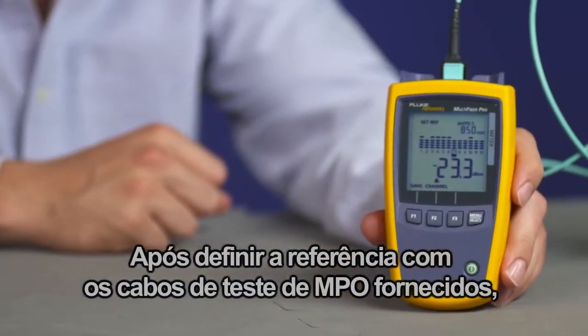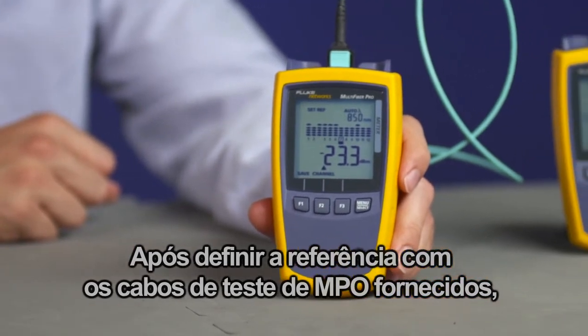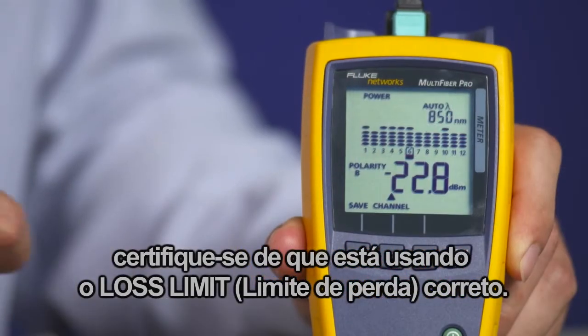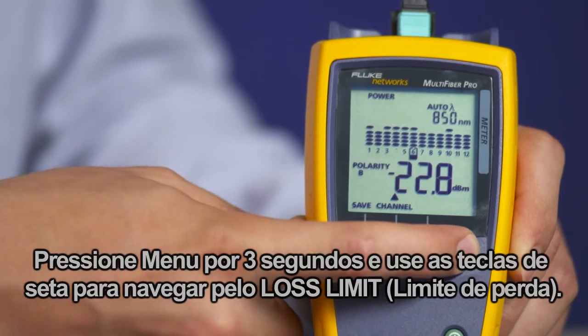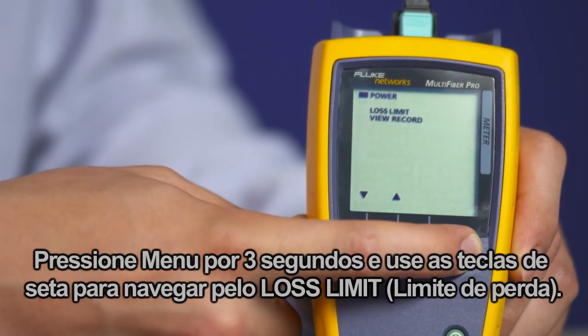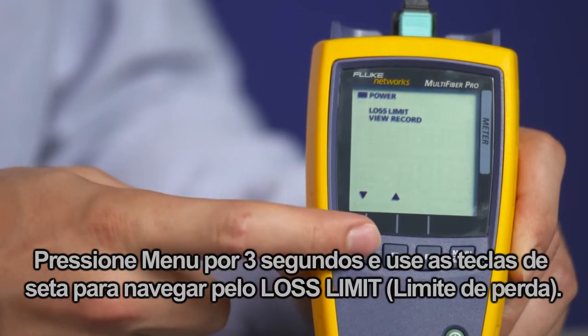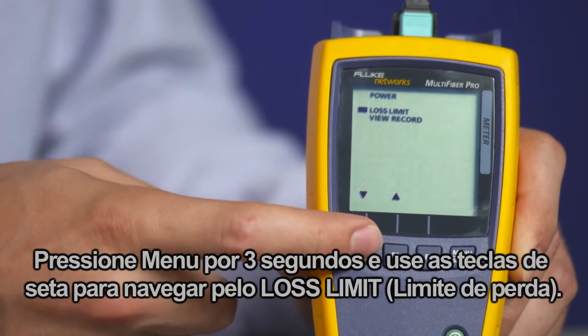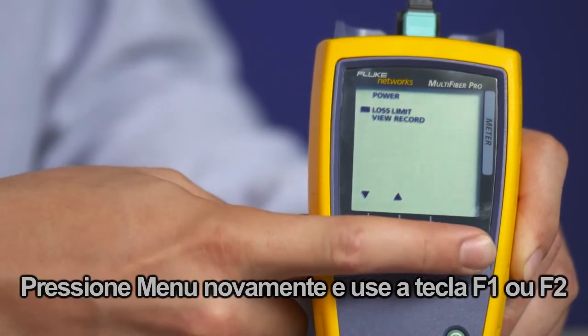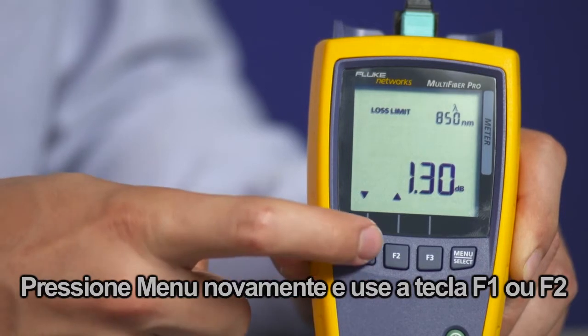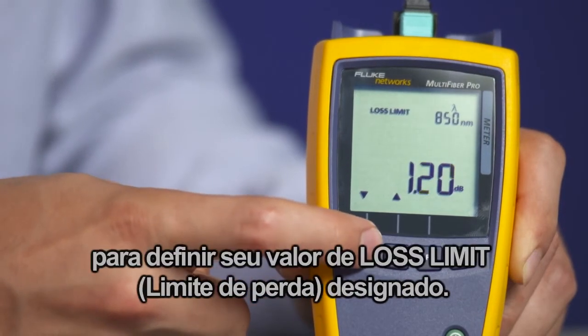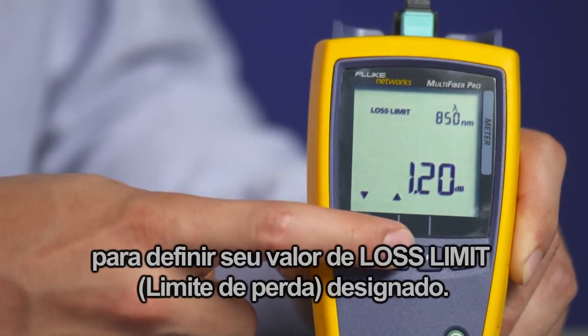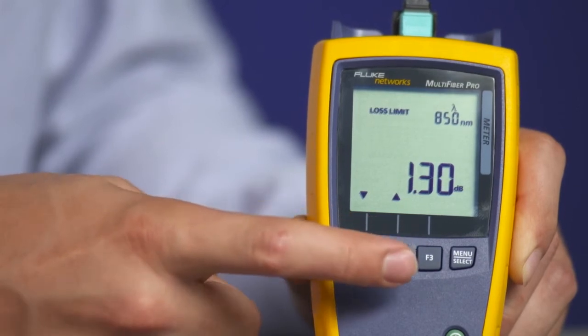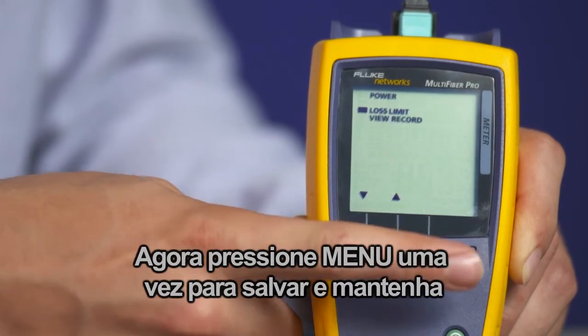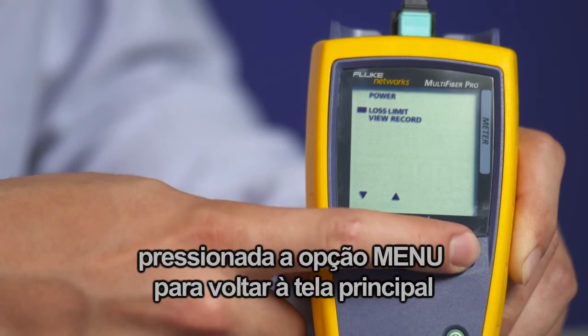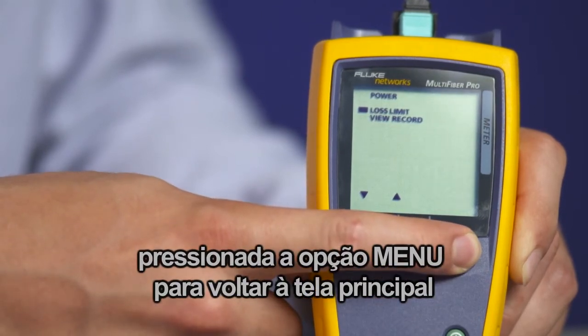After you've set the reference with the supplied MPO test cords, make sure you use the correct loss limit. Press menu for 3 seconds, then use the arrow keys to move to loss limit. Press menu again and use the F1 or F2 key to set your designated loss limit value. Now press menu once to save, and press and hold menu to go back to the main screen.